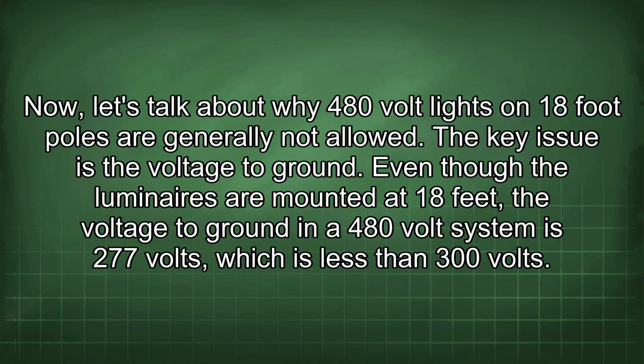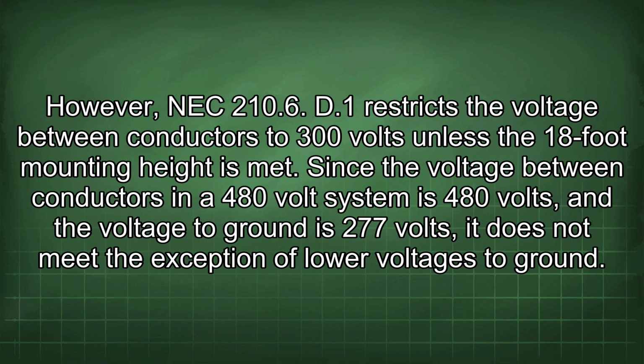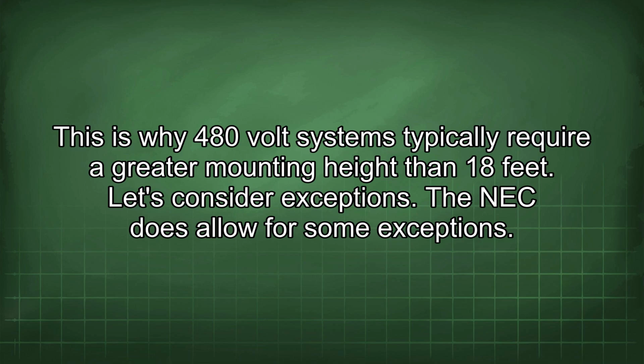Now let's talk about why 480-volt lights on 18-foot poles are generally not allowed. The key issue is the voltage to ground. Even though the luminaires are mounted at 18 feet, the voltage to ground in a 480-volt system is 277 volts, which is less than 300 volts. However, NEC 210.6(D)(1) restricts the voltage between conductors to 300 volts unless the 18-foot mounting height is met. Since the voltage between conductors in a 480-volt system is 480 volts, and the voltage to ground is 277 volts, it does not meet the exception of lower voltages to ground. This is why 480-volt systems typically require a greater mounting height than 18 feet.